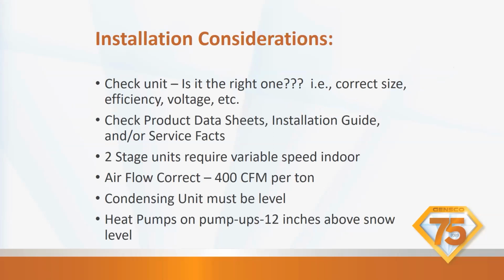So, installation considerations. When you get the equipment at your job site, you want to make sure it's the right equipment. Make sure it's the correct size, the correct efficiency, the correct voltage. I've had units come in a box that had the wrong information on the box. It was a furnace. We had a downflow furnace in an upflow box. The guys looked at the box, said, "Oh yeah, great," and installed it. They took the covers off the front and, oh geez, it's the wrong furnace. So if you just look at the stuff before you install it, you're going to save yourself a whole heck of a lot of time.